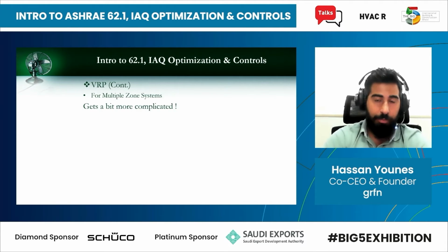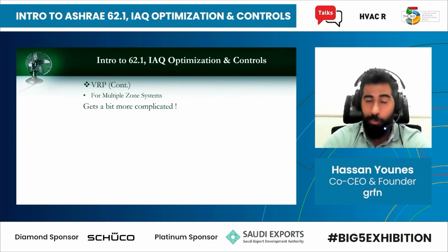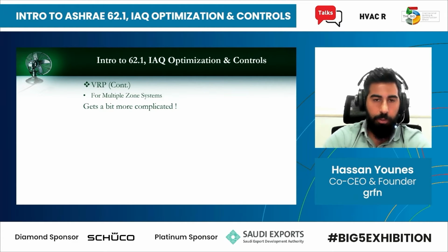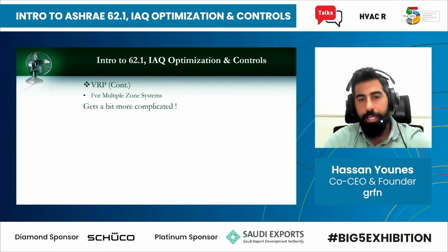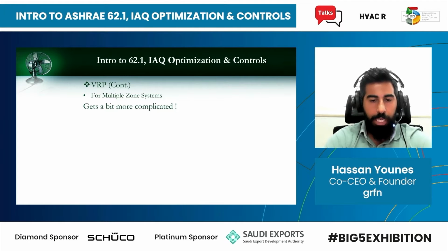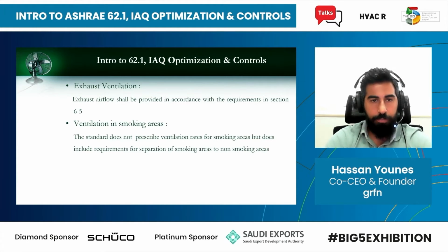Now, for multiple zone systems, if you have an air handling unit that has outside air and some return air, and you're supplying, let's say, more than 2 rooms, then it gets more complicated, and you need to do a little bit more calculation there. If you're interested in that, at the ASHRAE Global Training Center I gave a course on 62.1 that covers that part. If you have air handling units, especially with VAV boxes, then it becomes more complicated, and you need to apply more steps to get to the required air intake value on the outdoor air handling unit, or the air handling unit in this case.